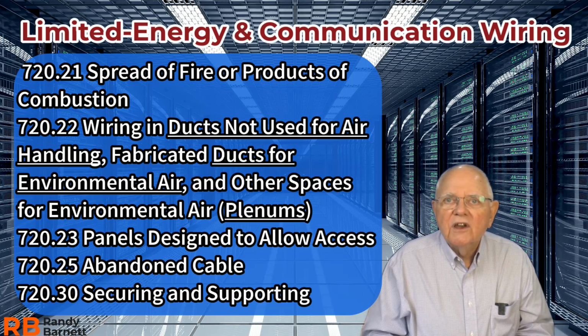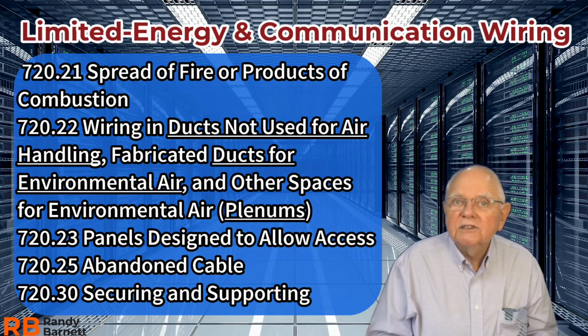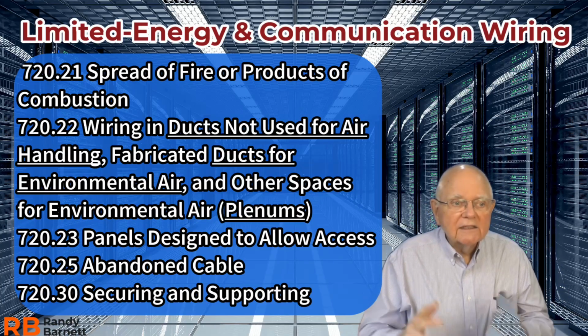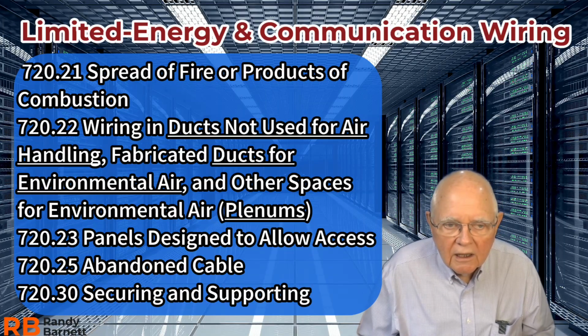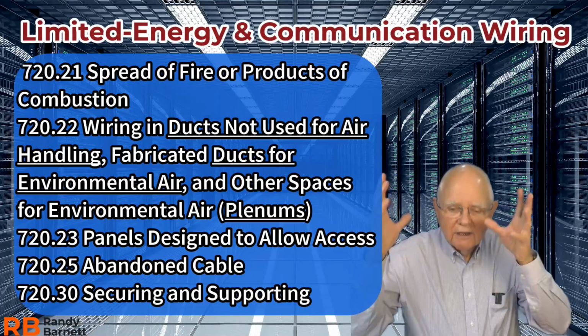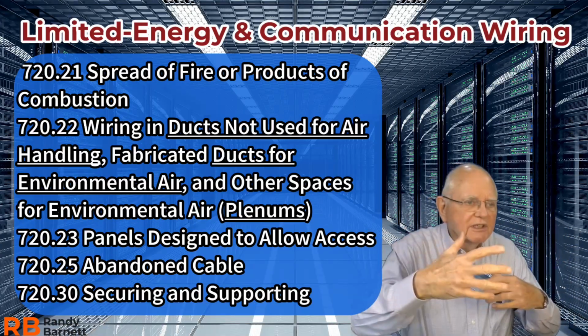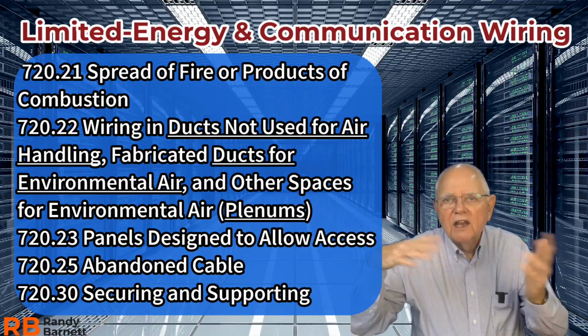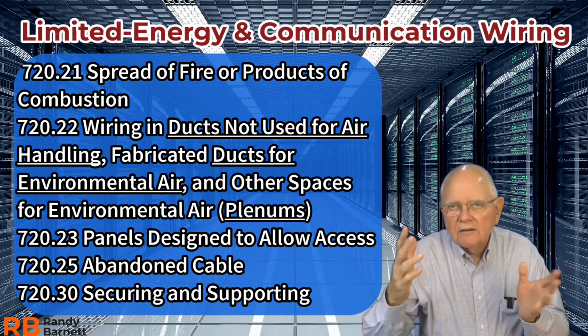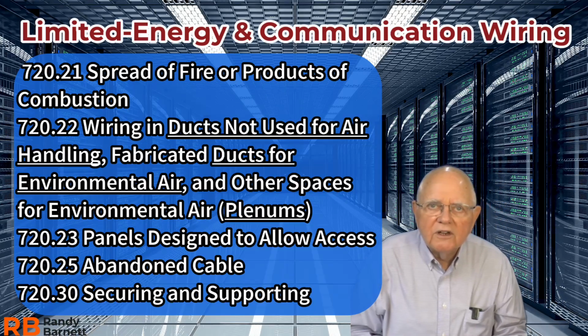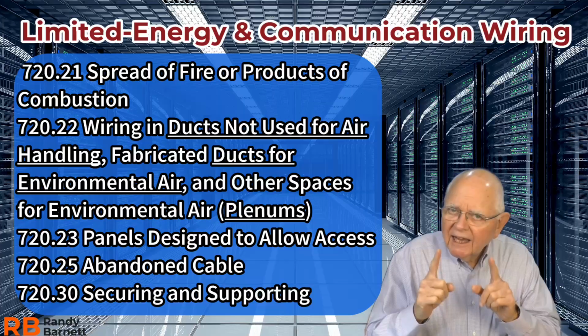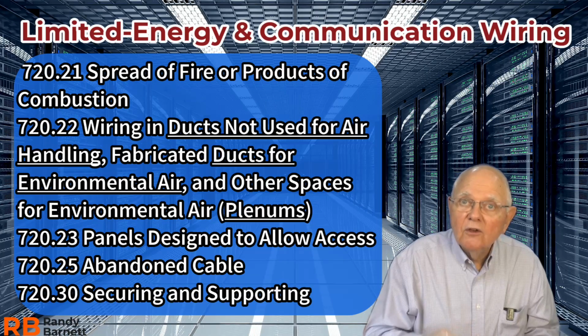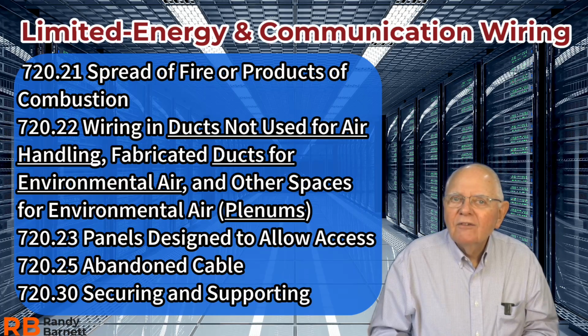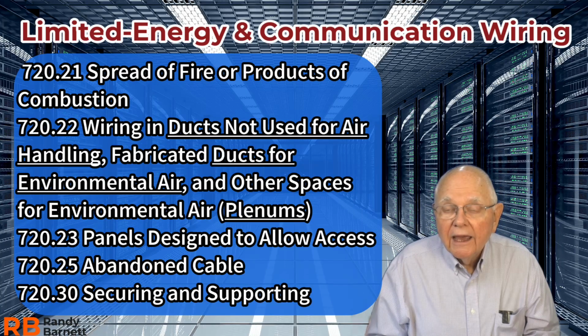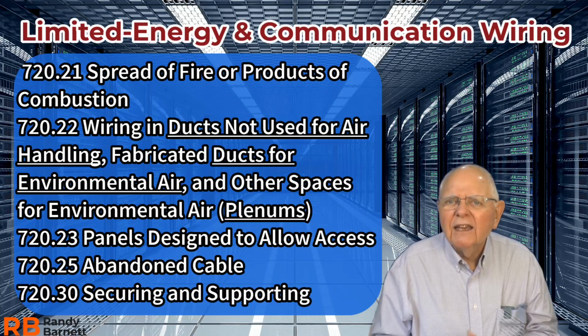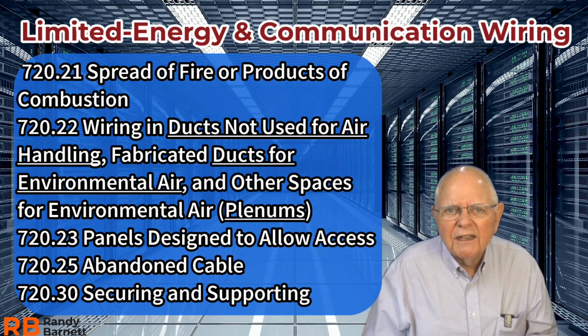Now, the second item it talks about is ducts, fabricated ducts for environmental air. So now back at the shop, they've taken some sheet metal and made up some ductwork, and they're going to run that from the rooftop unit down into my building, and they're going to have some sensors in there and some dampers and things like that, and we've got to be able to control all of that and get feedback from the sensors, whatever it is we need. And so we can run limited energy systems within those fabricated ducts for environmental air. However, they say, well, only if it's really necessary. And then it gives provisions for uses of things like MC cable, MI mineral insulated cable, and so forth.